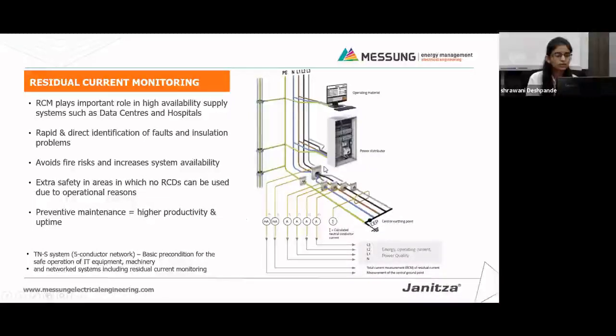Now, how are these residual currents measured? As you could see in the image, the RYB phases, that is L1, L2, L3 and neutral, are connected together through a summation CT. A summation CT is put on all 4 phases, and one CT is put on the earth terminal, earth conductor, and both these CTs are in milliampere rating. So when the result of this CT is not equal to 0, meaning if it is greater than 0, then we could conclude that we have a fault in our system. And if this result is 0, then we could conclude that our system is fault free.